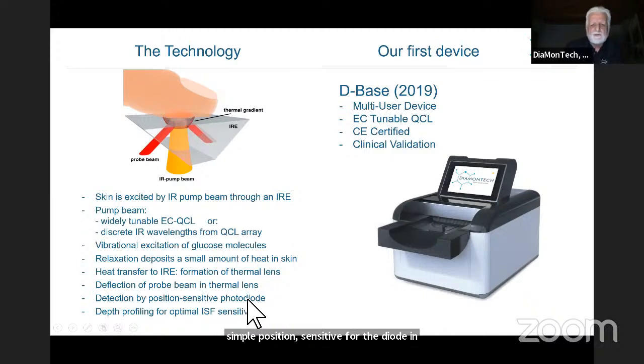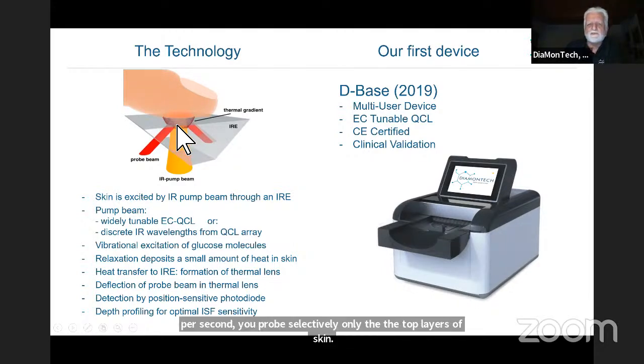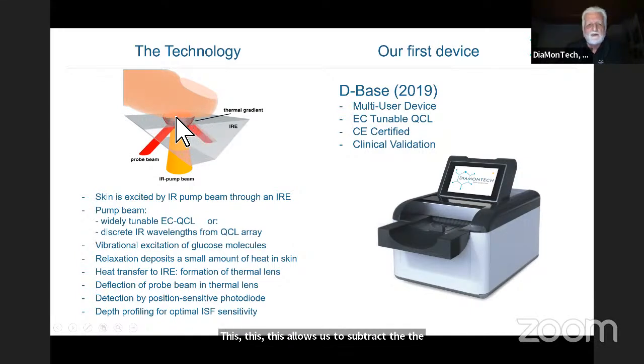In addition, we use a depth profiling technique, which is a specialty of the photothermal technique, because as we use different pump frequencies, we can probe different layers. Briefly said, if you use a very low frequency for the modulation of the infrared pump beam, you can select the entire optical penetration depths, say around 0 to 100 micrometers. And if you use a higher frequency, say, for example, 200 pulses per second, you probe selectively only the top layers of skin. This allows us to subtract the contribution of the stratum corneum, which is a layer that does not contain relevant amounts of glucose. So we have direct access to the glucose in the interstitial fluid of skin.